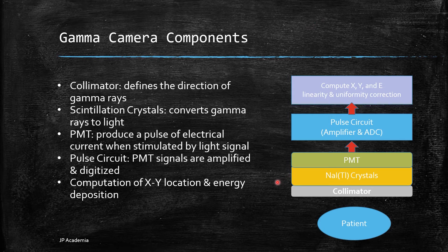The photomultiplier tube, shown here in green, also called the phototubes, are electronic tubes that produce a pulse of electric current once stimulated by weak light signals from the crystals. Signals from the PM tubes are then sent to the digital position circuit. This computes the X and Y location of each scintillation event.